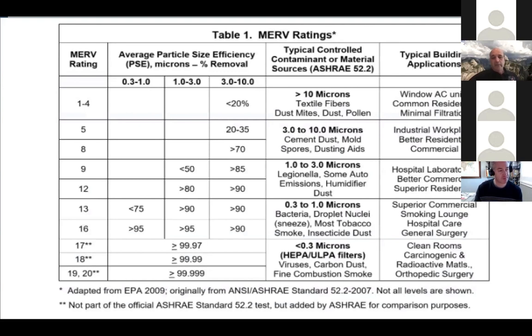And it'll operate in most of your mechanical systems. There's only a few cases around that some of the older systems won't be able to tolerate MERV 13, but for the most part, 95 to 98% of systems will be able to tolerate a MERV 13 filter. And then they remove about 90% of the particles in the air.